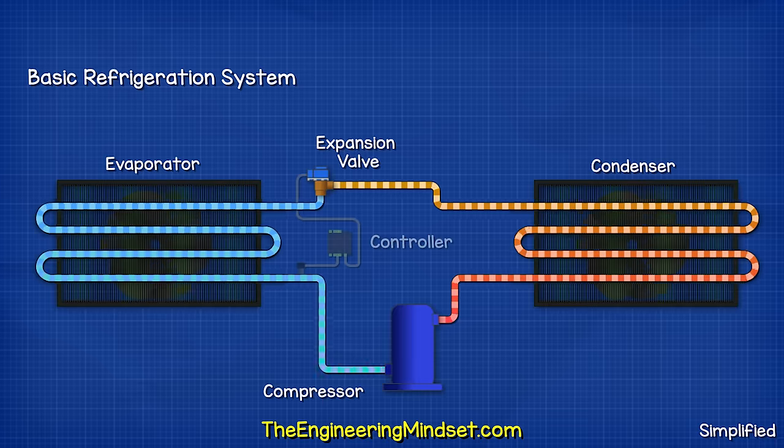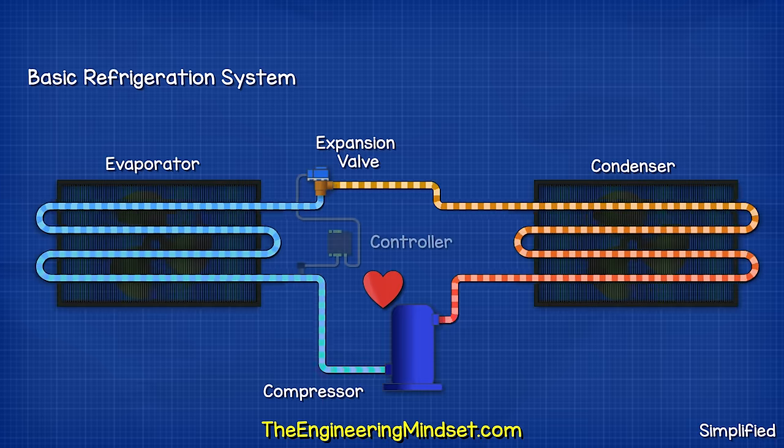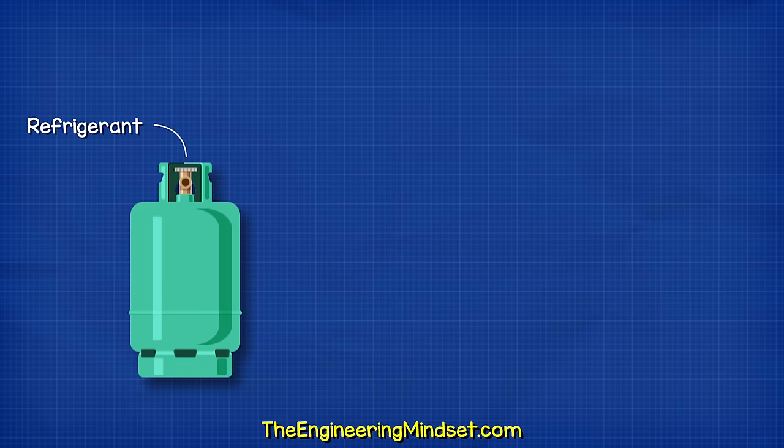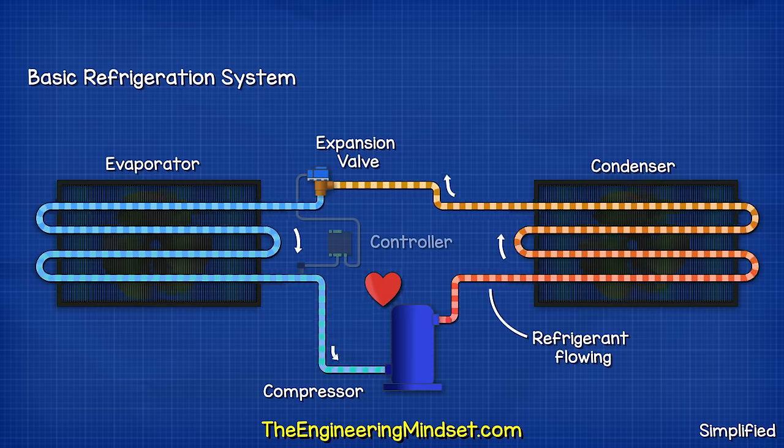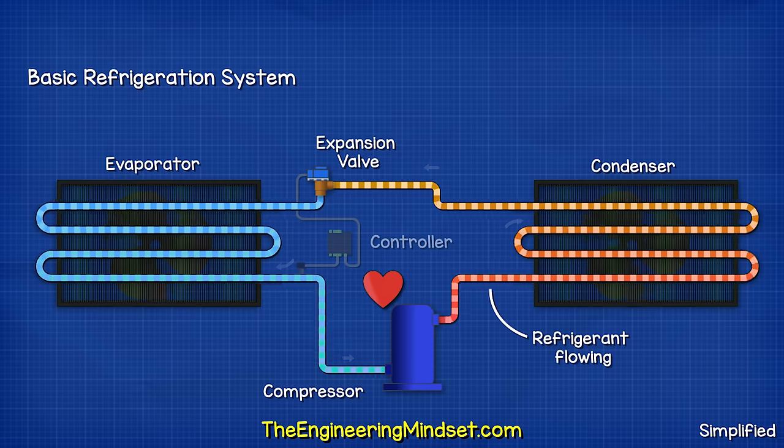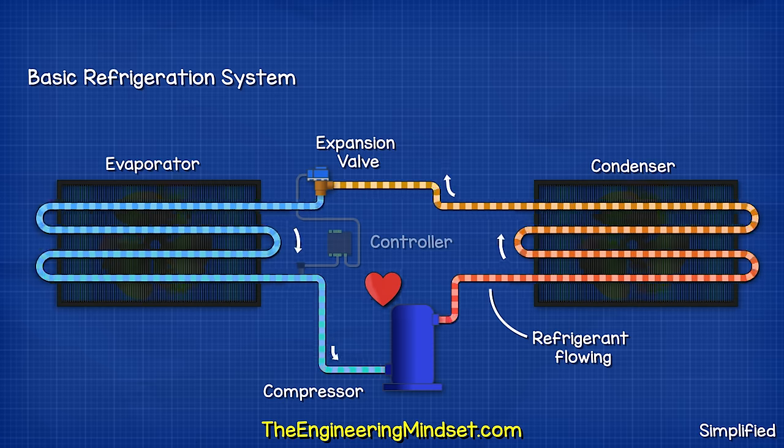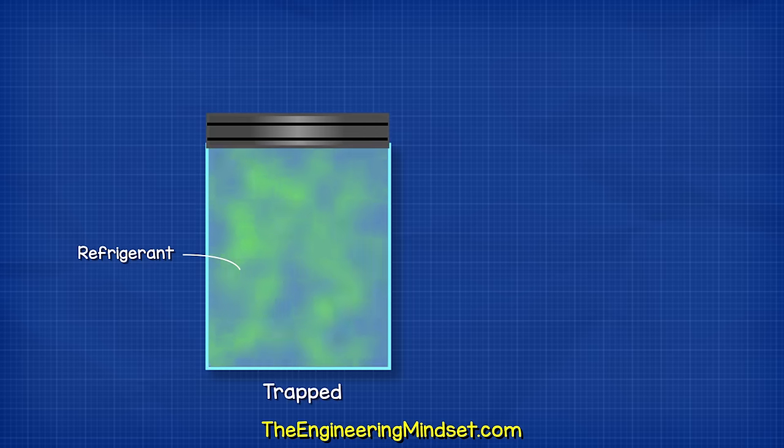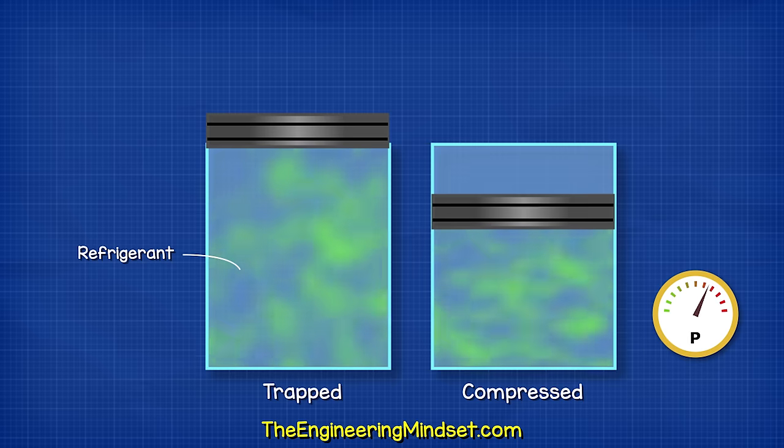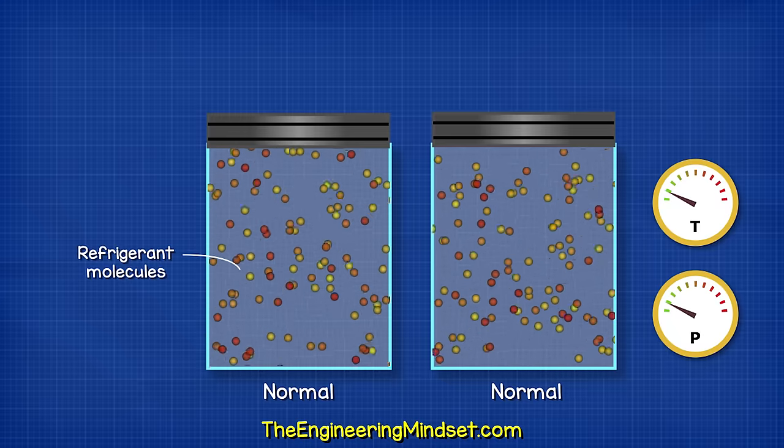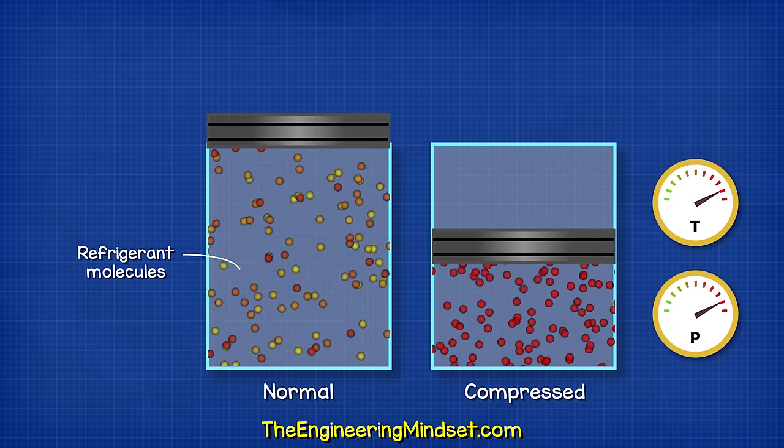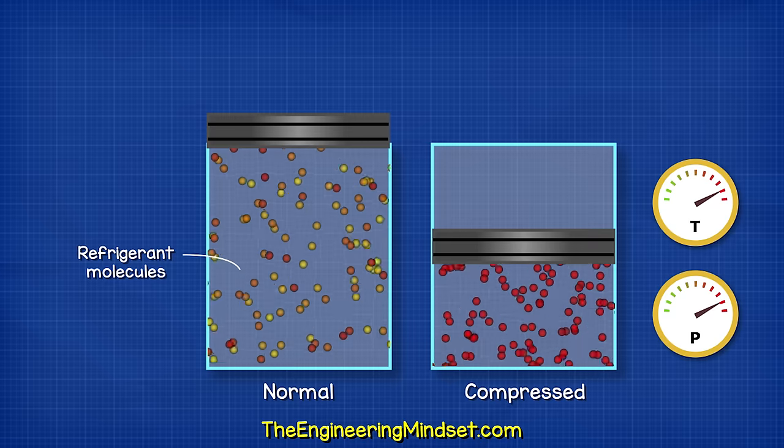Compressors are the heart of the refrigeration system. They push the refrigerant between all of the components. The refrigerant is a special fluid which can easily change between a liquid and a gas. The compressor pushes this around the entire refrigeration system, through the condenser, the expansion valve and evaporator, and then back to the compressor. Compressors simply trap a quantity of refrigerant and then compact this into a smaller volume to increase the pressure. The molecules are then tightly packed together and so they collide more often. The pressure and the temperature will therefore increase.